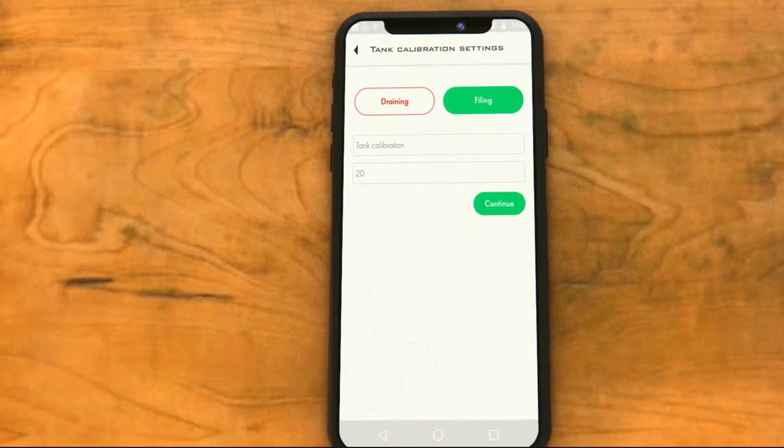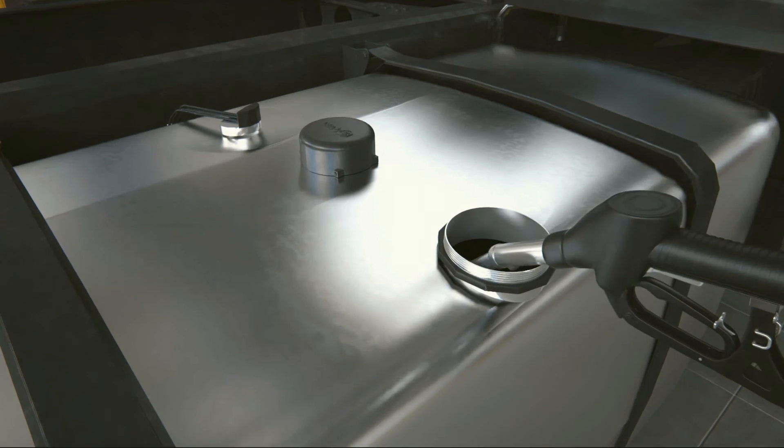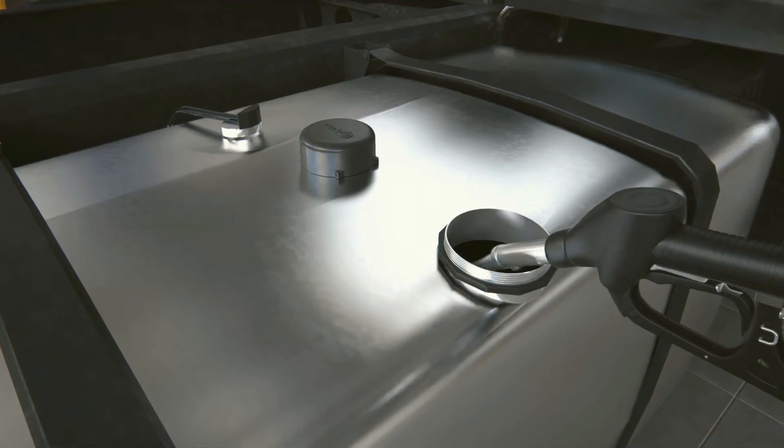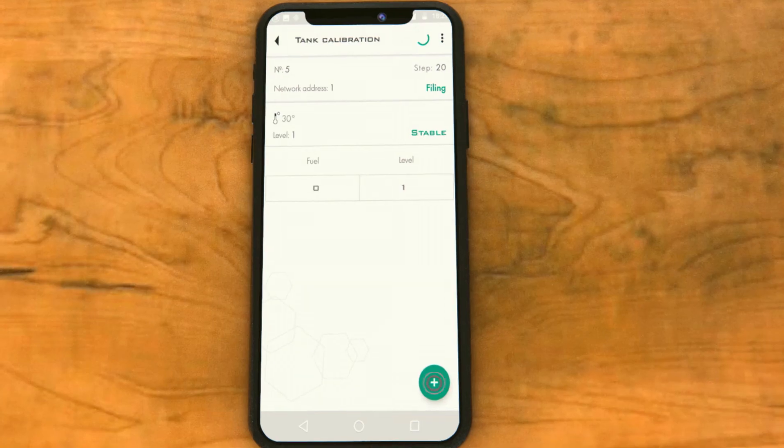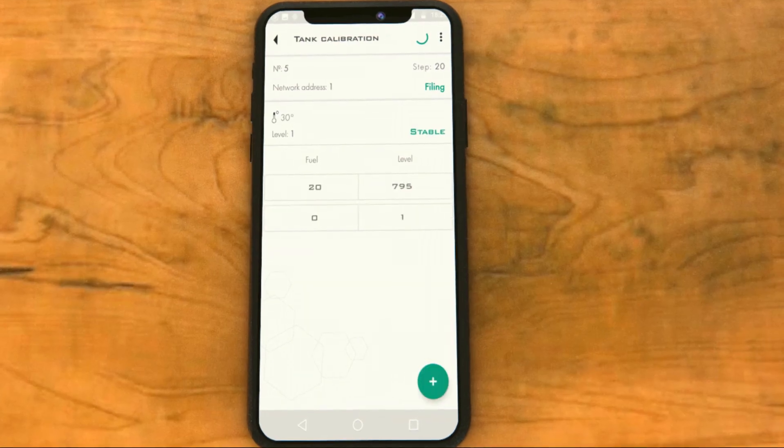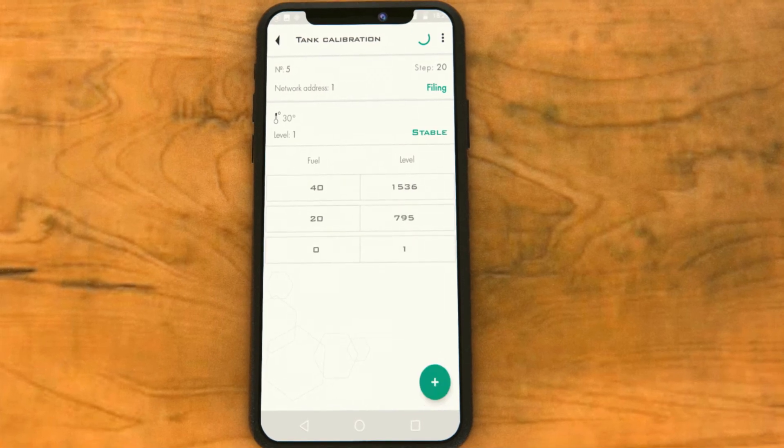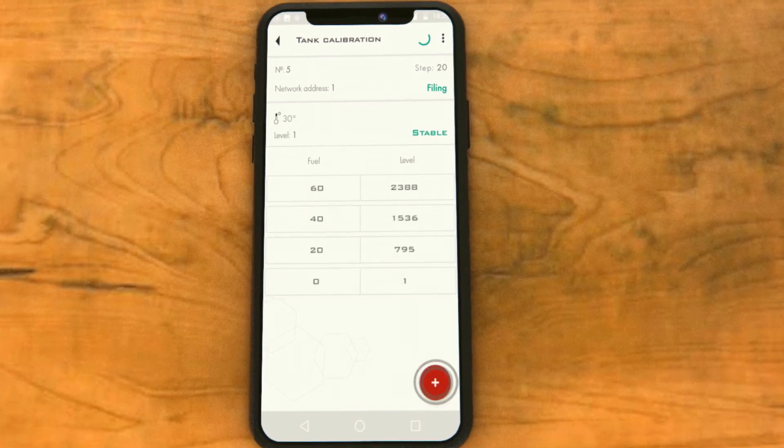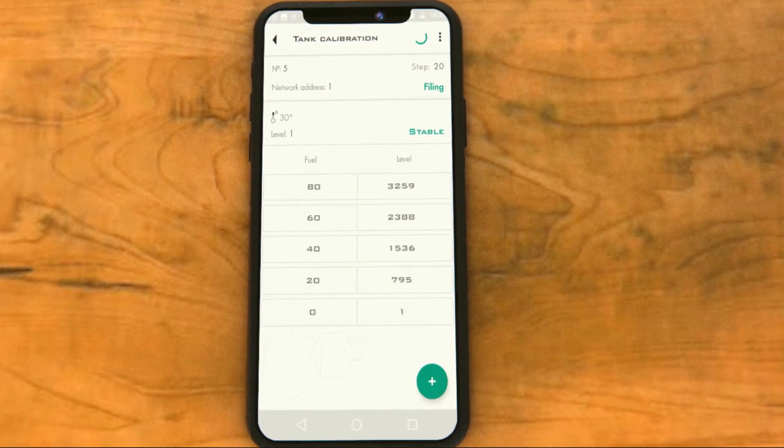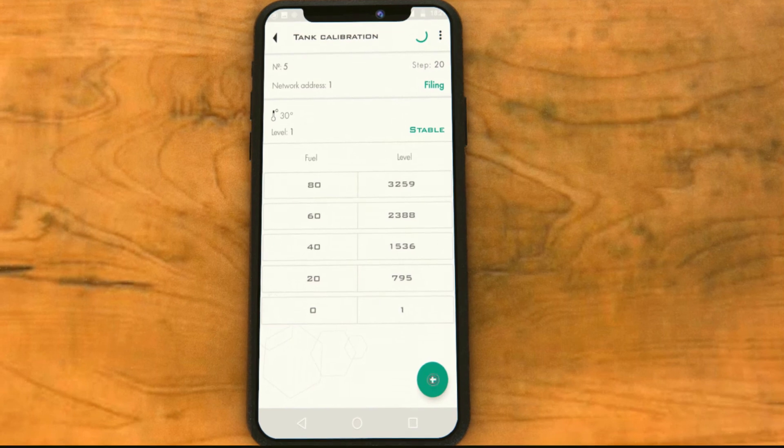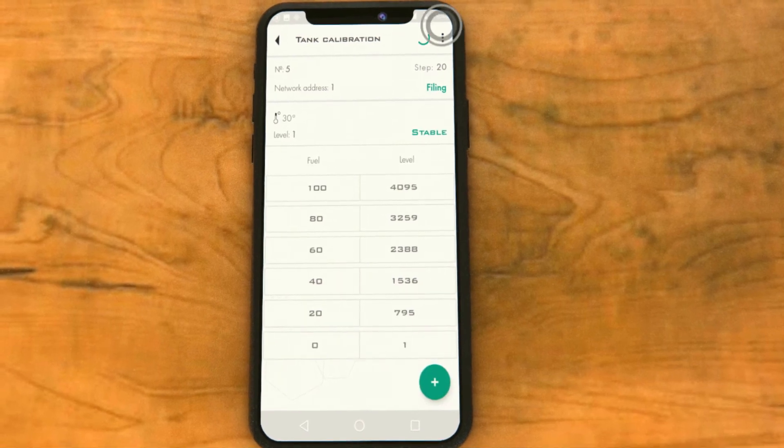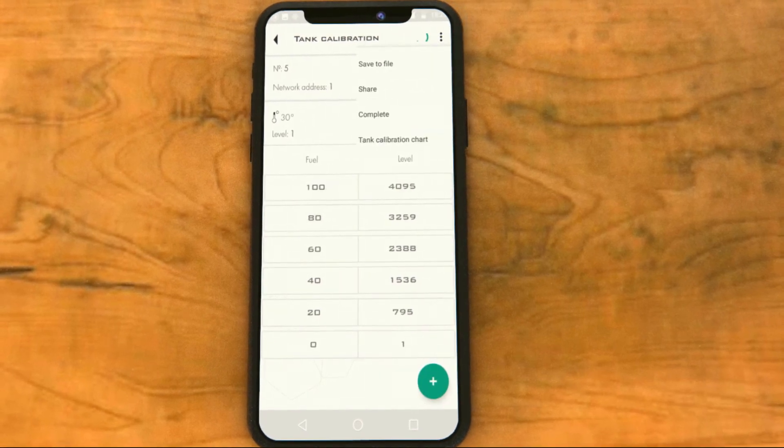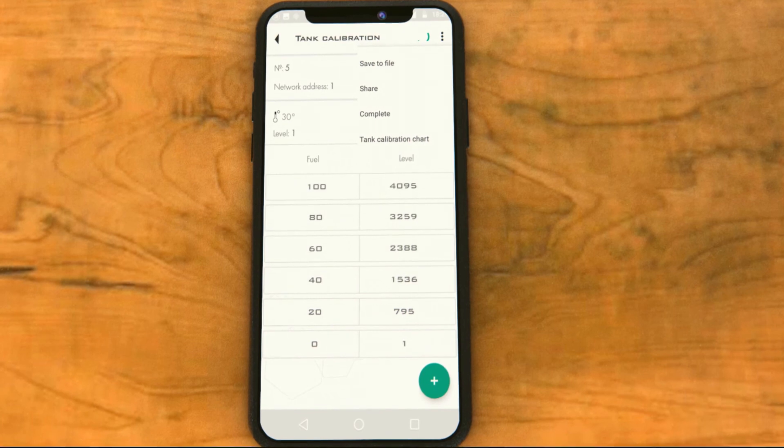Pour a portion of fuel into the tank via the filling neck. While adding more portions, 20 liters each for example, hit the plus button after each portion is added and the level is stable. Continue until the tank is full. Once the tank is filled, hit the three dots in the upper right corner and select save file.